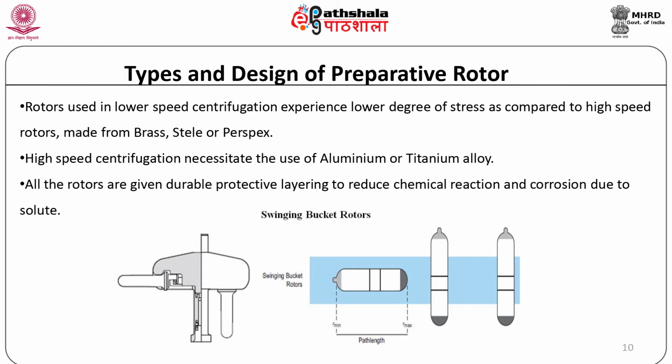Swinging bucket rotors. It has buckets that start off in a vertical position, but during acceleration they swing out to a horizontal position. Hence, the solution in the tube is perpendicular to the axis of rotation and parallel to the applied centrifugal force. The tube returns to its original position during deceleration. Particles in the centrifugal field fan out radially from the center of rotation rather than sedimenting in parallel lines. Undesirable swinging effect that causes mixing of tube contents is produced during rotor acceleration and deceleration.